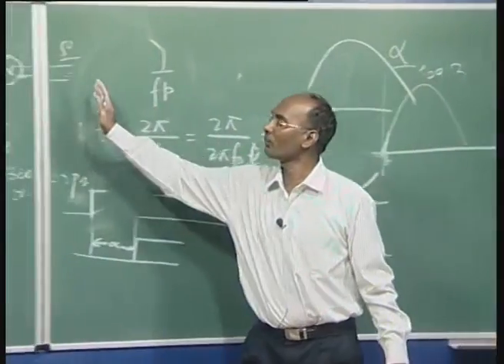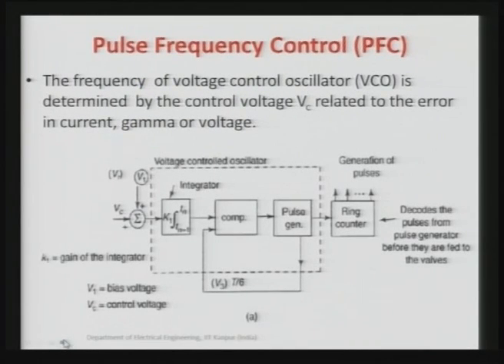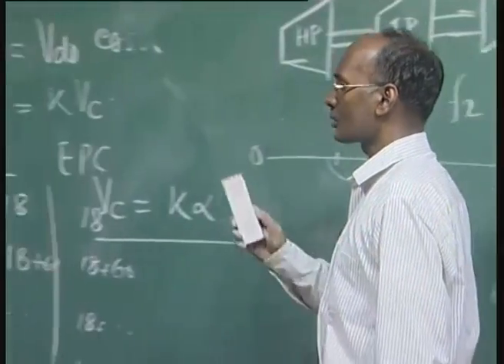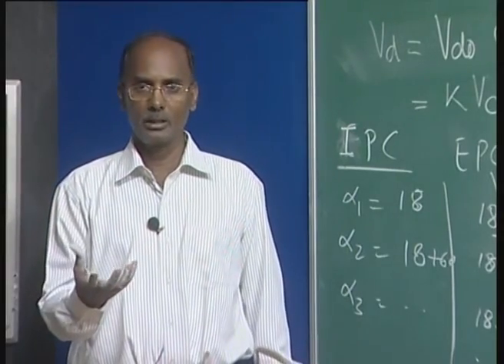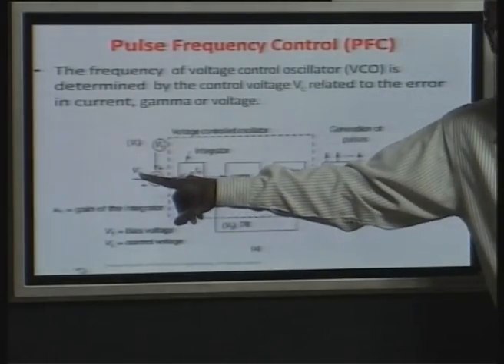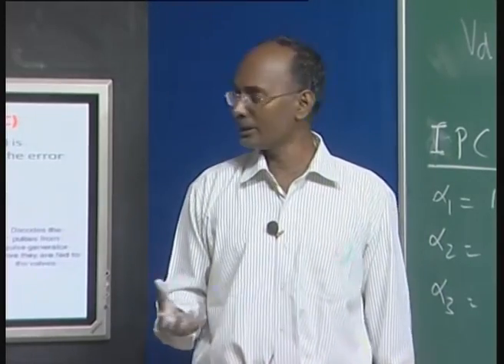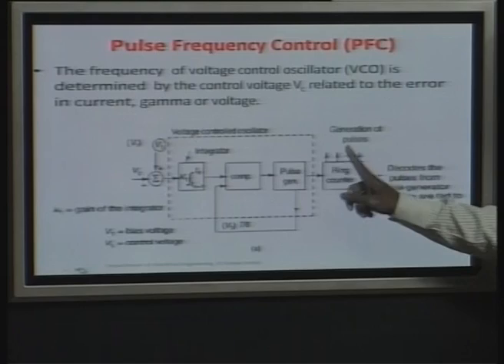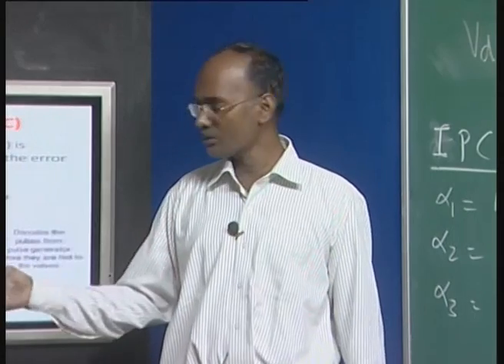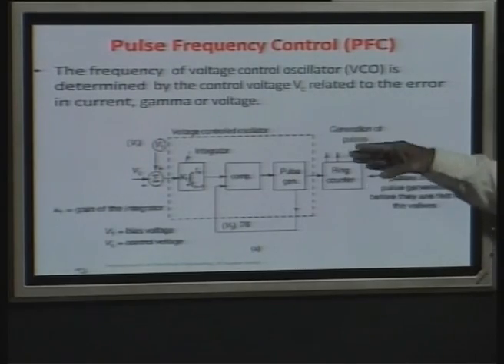This problem only occurs if a power plant is near the HVDC link; otherwise, because of negative damping, there is no problem. Now let us start with pulse frequency control (PFC). The frequency of the voltage-controlled oscillator (VCO) is determined by the control voltage V_C. The VCO comprises an integrator, comparator, and pulse generator. Once it generates pulses, a ring counter shifts them by 60 degrees automatically, since for valve 1 it is alpha, for valve 2 it is alpha+60, for valve 3 it is alpha+120, and so on.